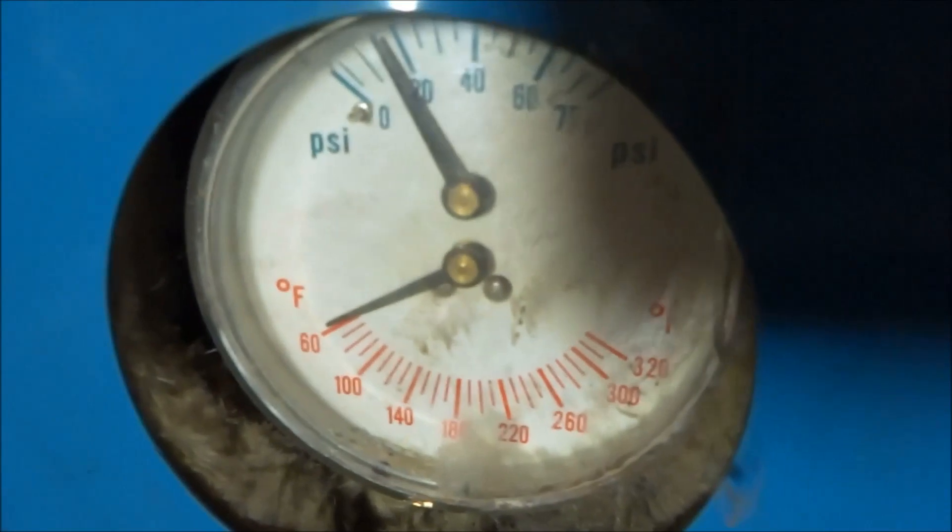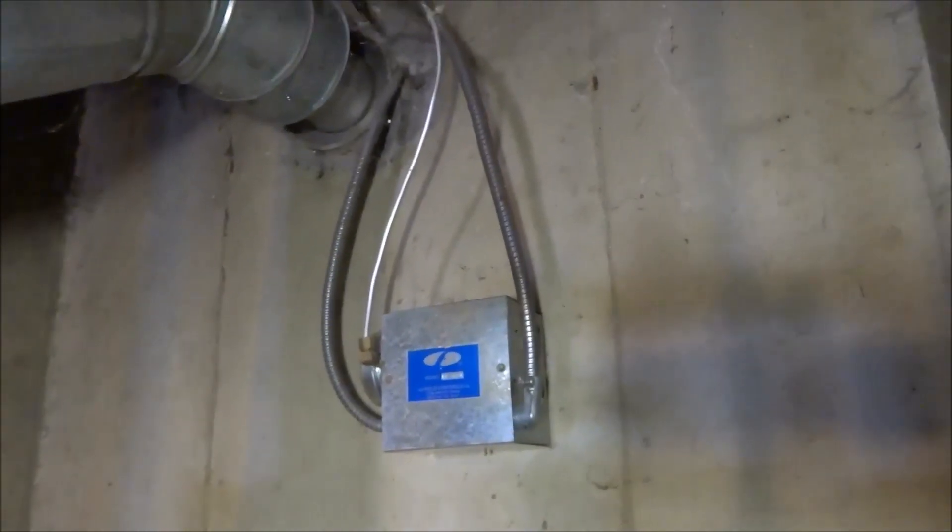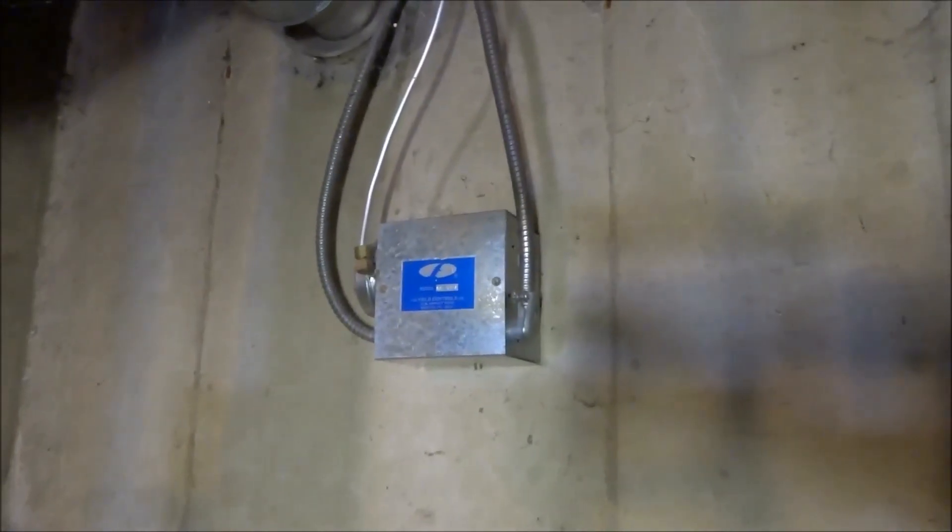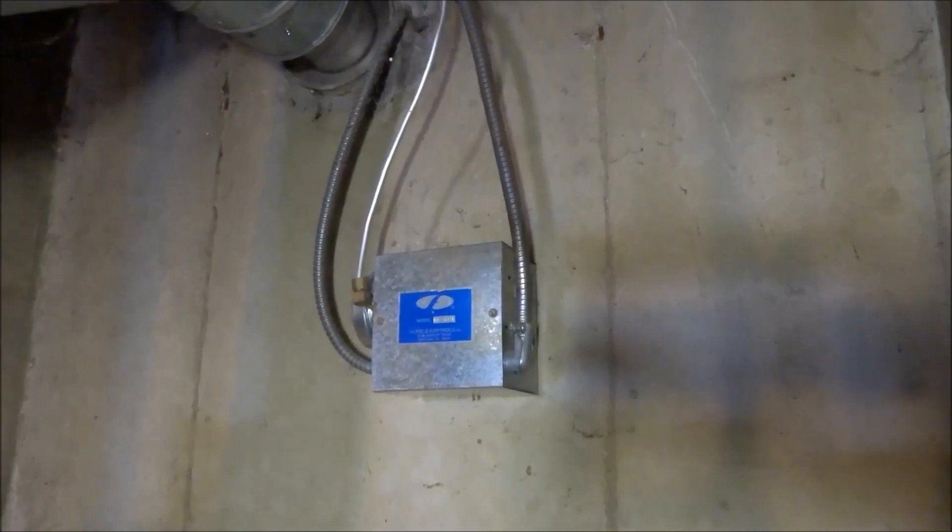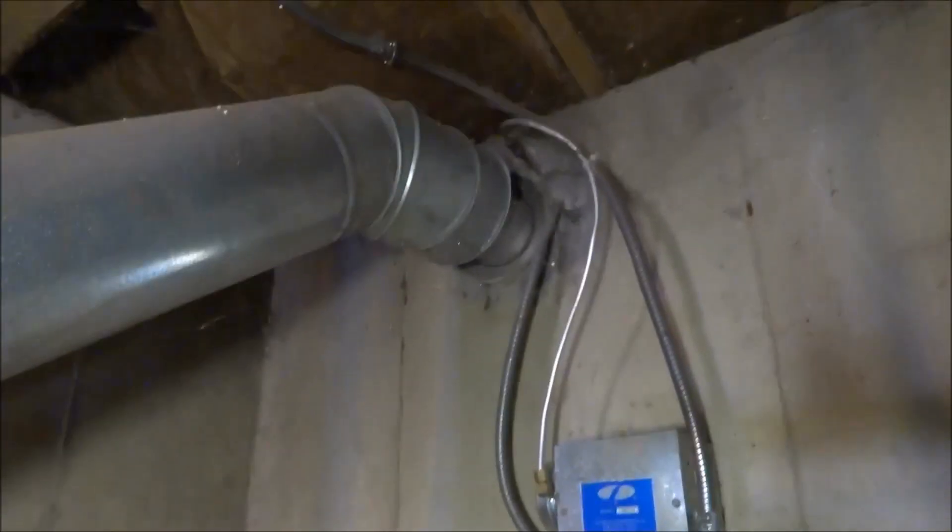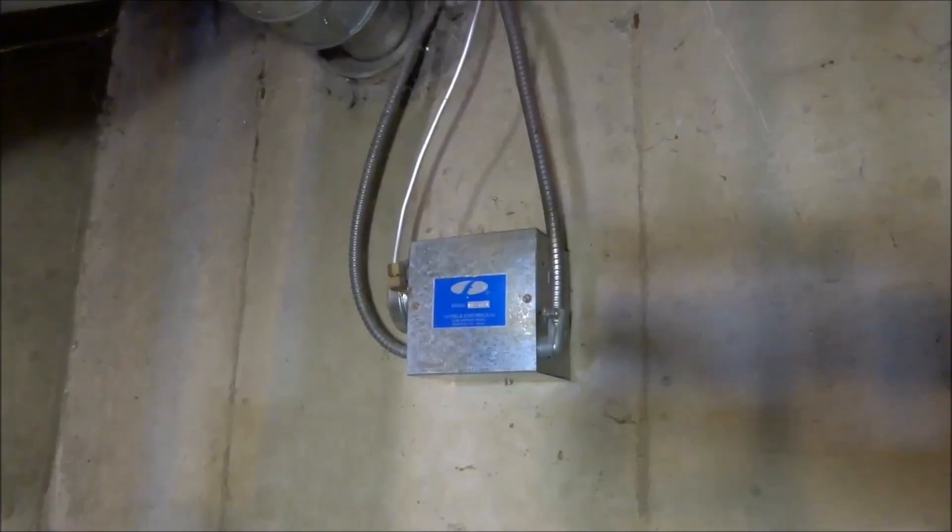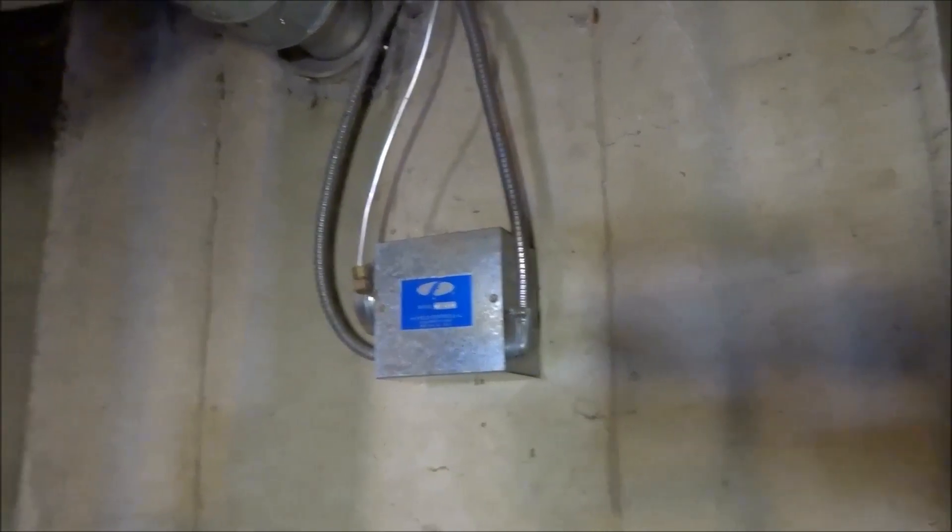I don't hear the power venter running. I'm going to check that control, see what we got for power in there. Might be a bad motor. Let's see if we got power going to the control.